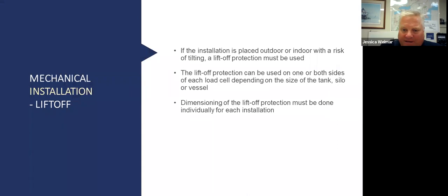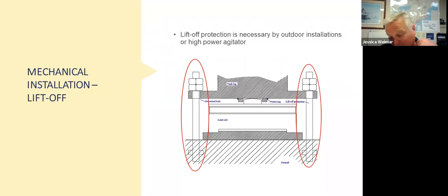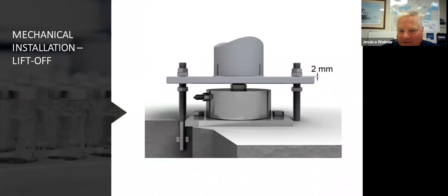One of the things you do have to think about is, I just told you, you don't need any way to mechanically support our load cell. That's true. But if you've got a tank outside or in a place where it might lift off, think about a big grain silo, if it could tip over and fall off, you need to have some sort of mechanical restraint on it. Our restraint is not as difficult to deal with as a strain gauge because we're only using it to stop the tank from tipping over. We use big holes in the legs here where the bolts go through so that they don't bind up. We leave plenty of room in the nuts so that it doesn't stop the unit from reading accurately. It's only there for a catastrophic situation. And you can see what I'm talking about here.